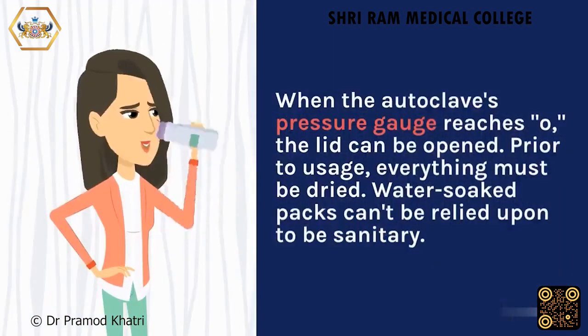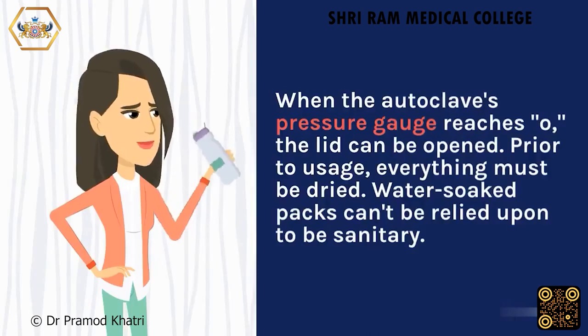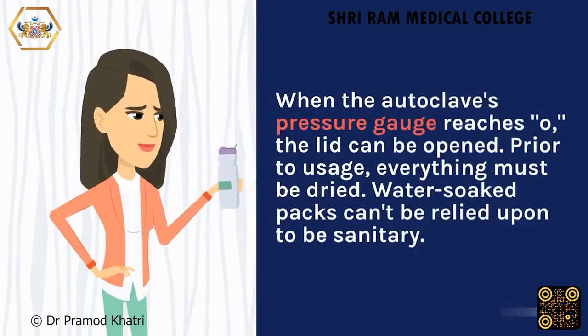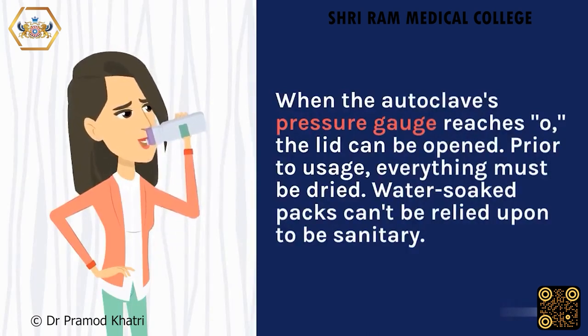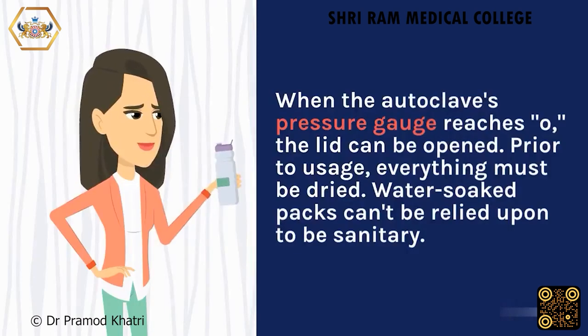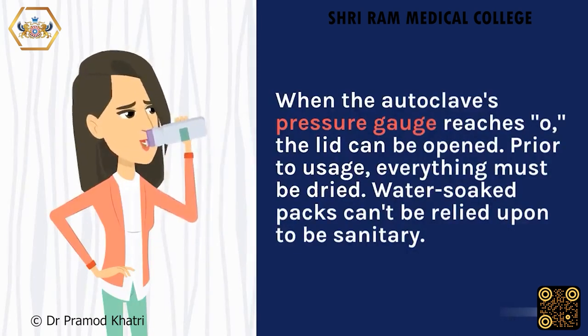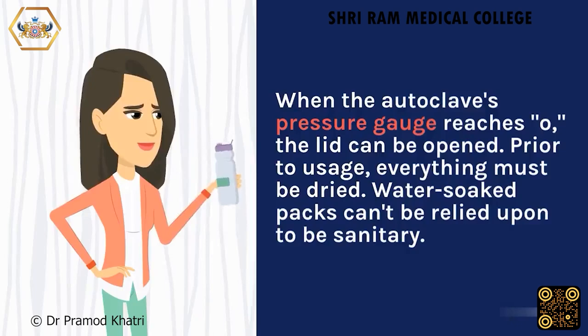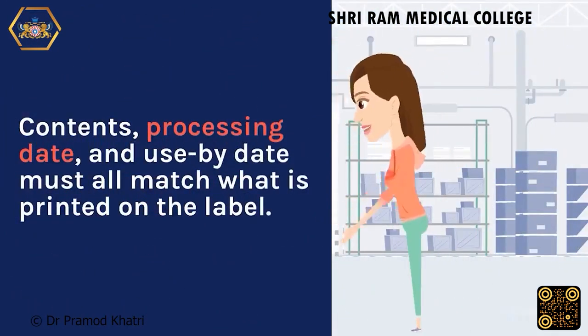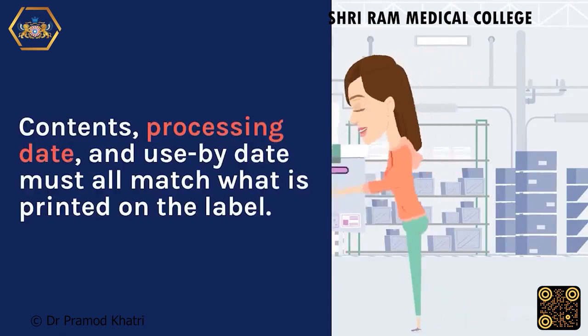When the autoclave's pressure gauge reaches 0, the lid can be opened. Prior to usage, everything must be dried. Water-soaked packs can't be relied upon to be sanitary. Contents, processing date, and use by date must all match what is printed on the label.